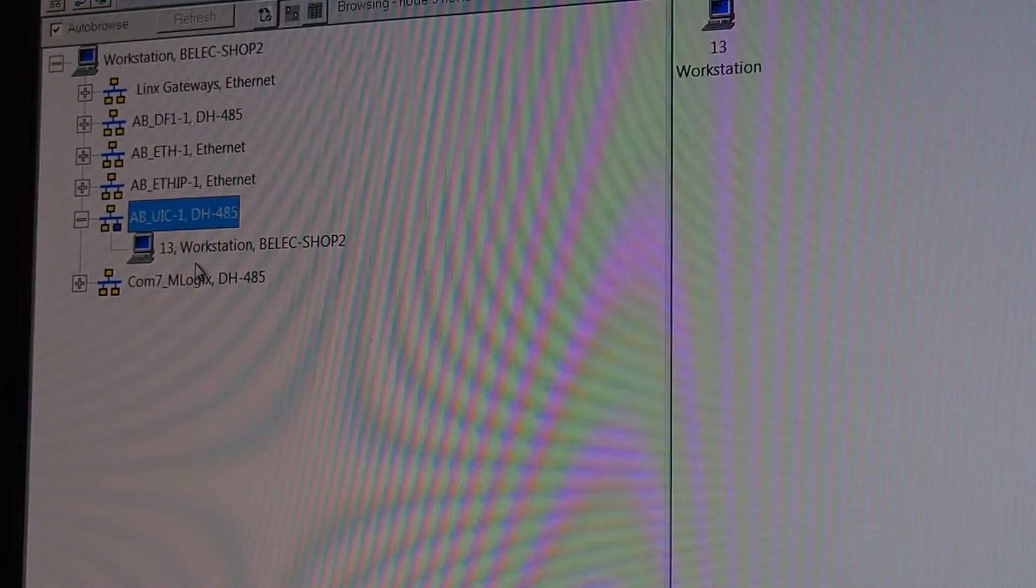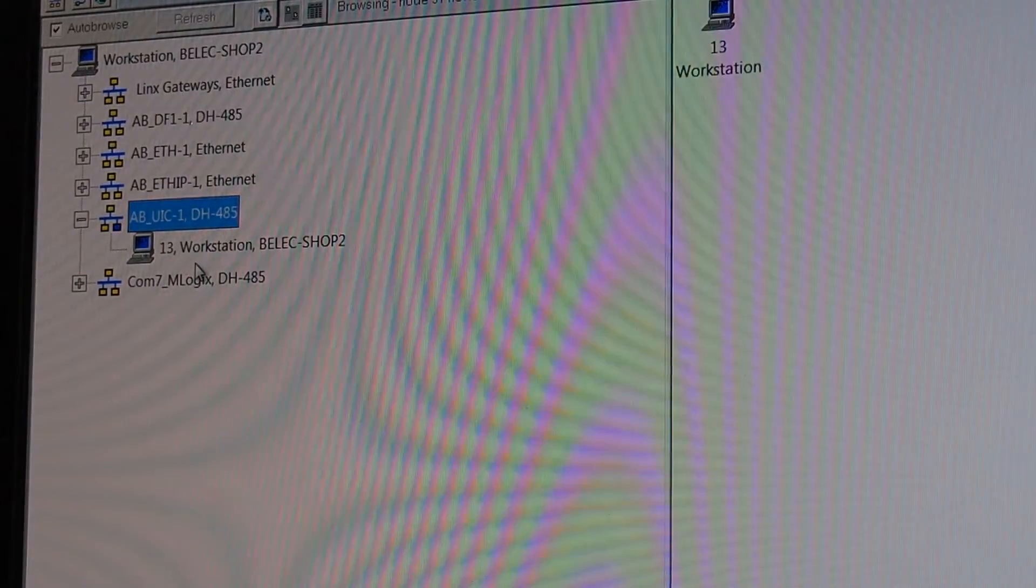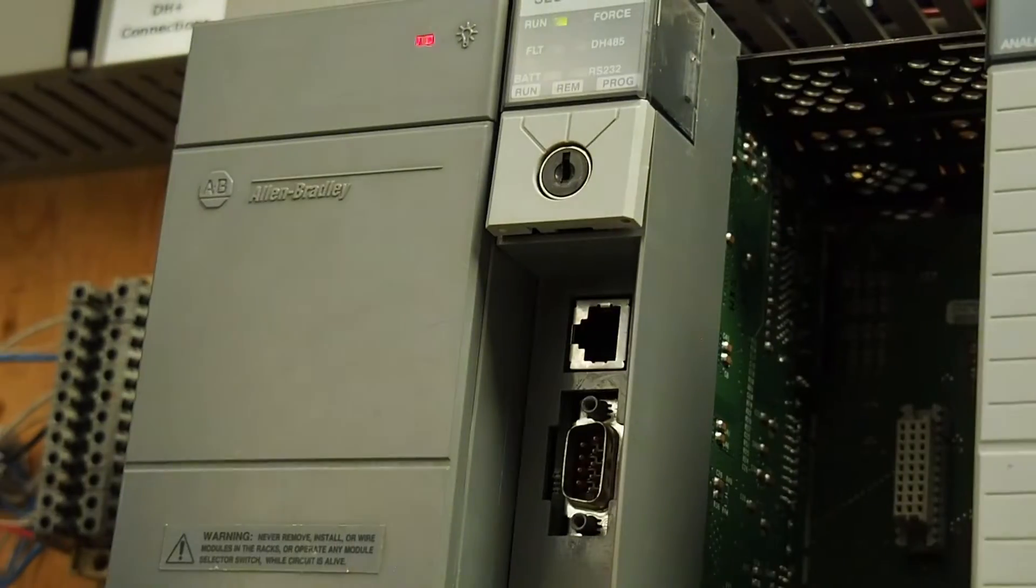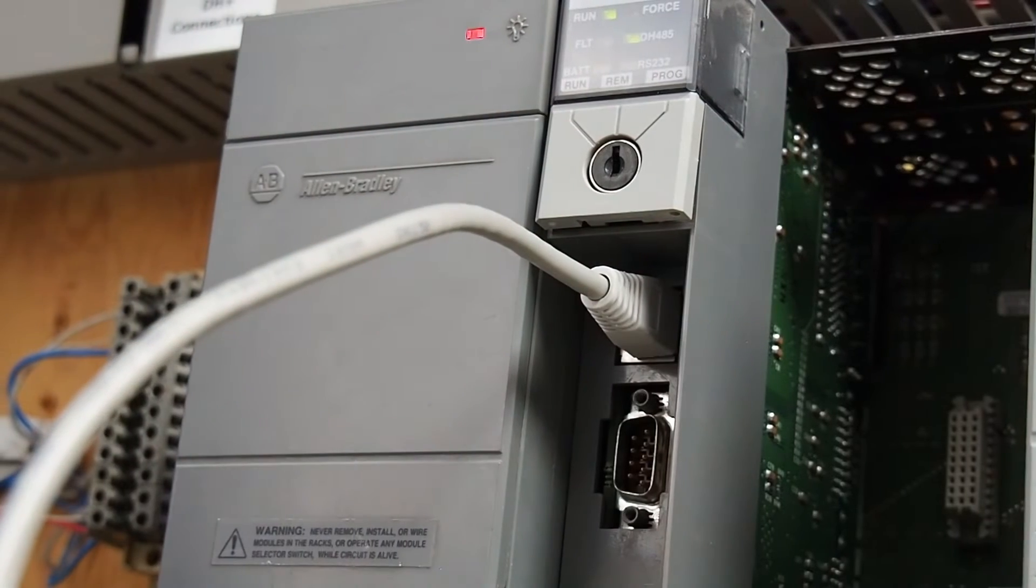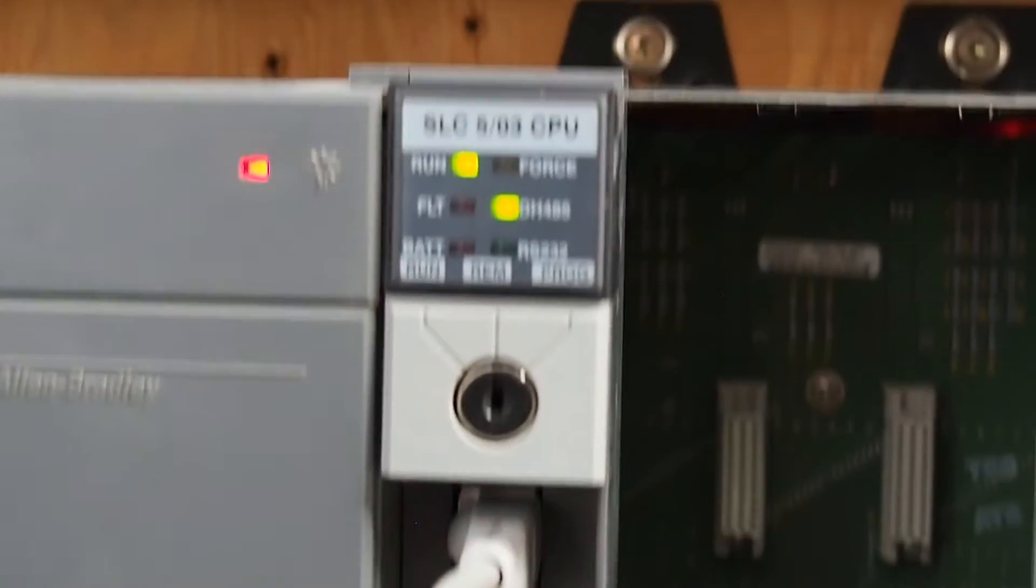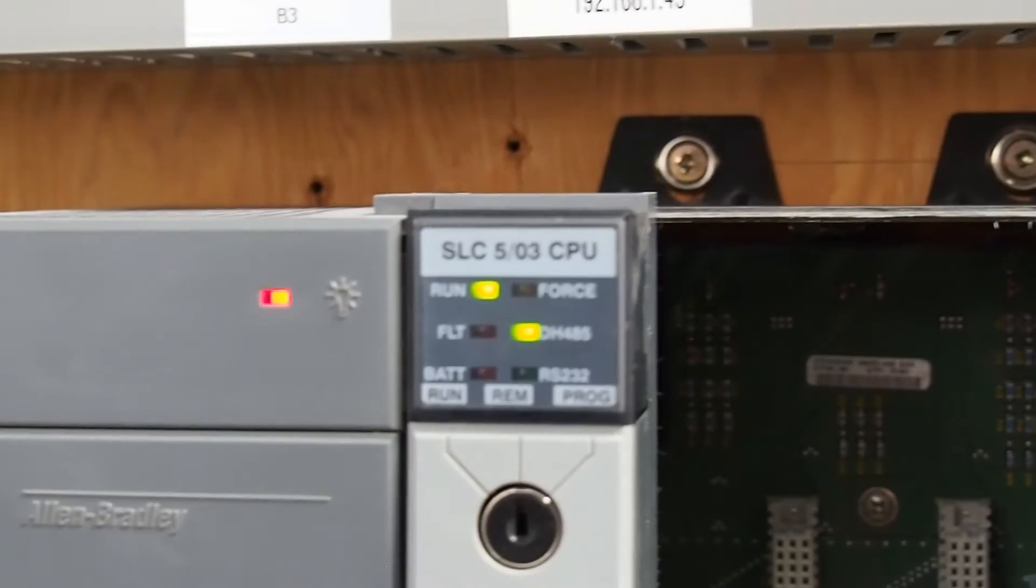So, we'll take our C13 cable. We'll plug it into the front. And this little switch here, really hard to see if I don't get it in the right spot. It has to be set on DH485. The other side is RS232, which you can use on all the processors. We'll just swing this around and plug this into our front port. And you can see it says it's seeing something on 485.